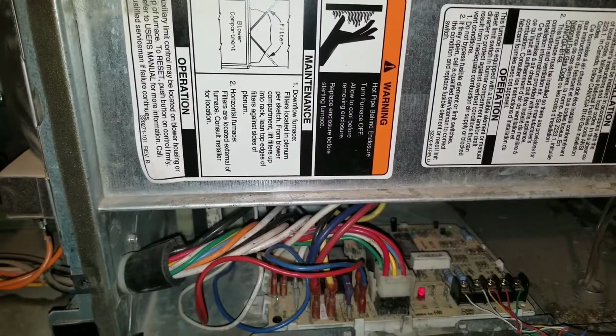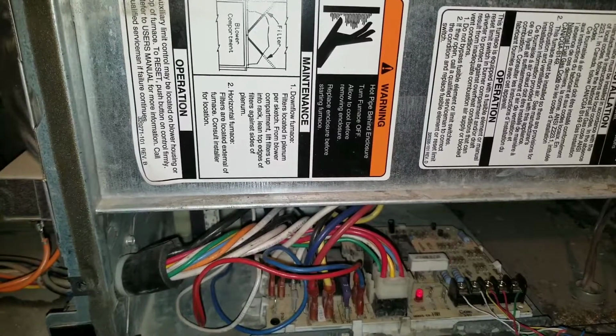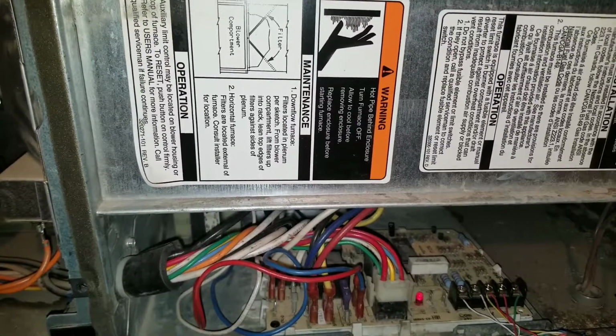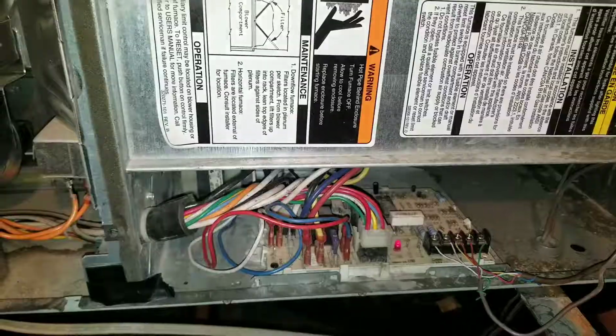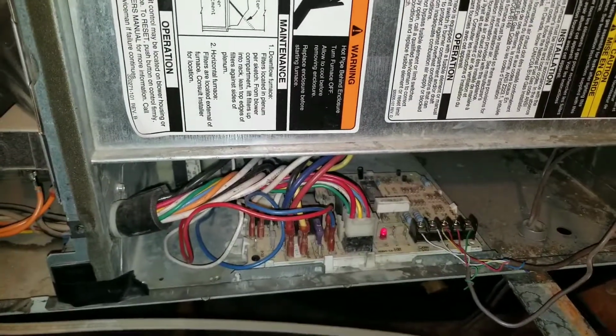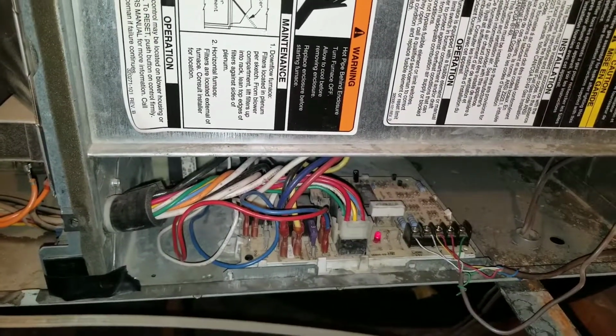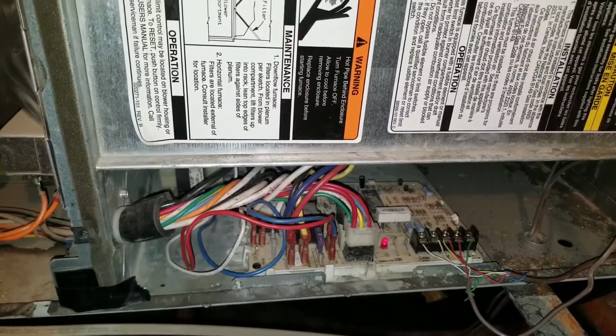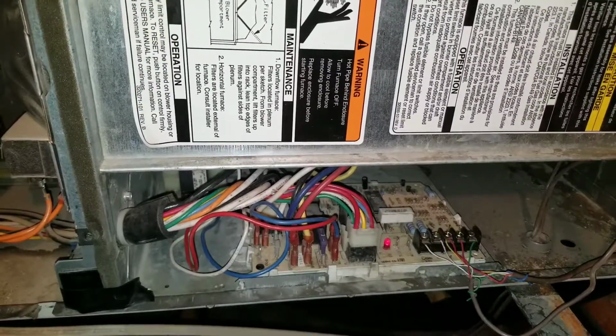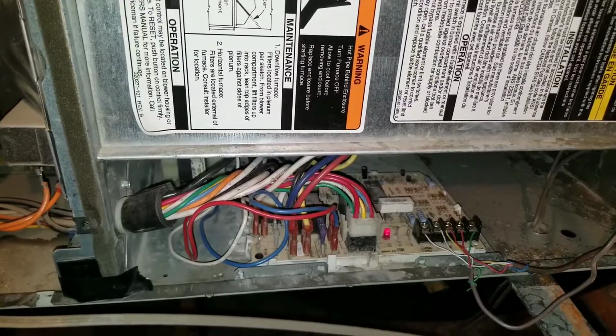This eliminates the need to go up and down and unnecessarily turn the thermostat off and on, cool, heat. This will be a way for you to basically jump your furnace board and test out each component individually. Especially if you find yourself troubleshooting for a low voltage short, it's very helpful to be able to jump the system here at the furnace board.